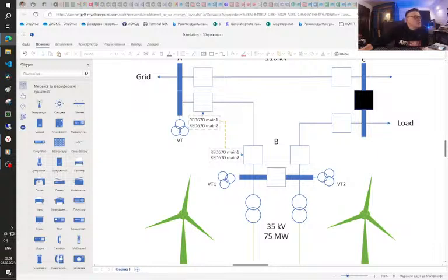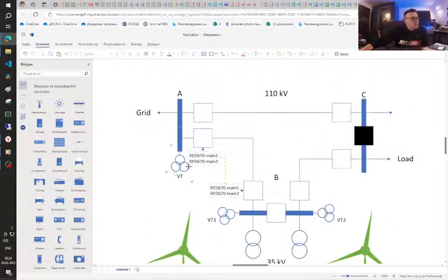The bus A is strong and bus B is weak, and the secondary side of the transformer at B is probably delta. Because of that, you can see that the current has the same magnitude and same angle in the current waveform. Yes, this substation A is very strong. I showed you a very simplified part of the grid, and there are more than 110 kilovolt lines and 330 kilovolt lines. So yes, this substation A is a powerful transmission substation.